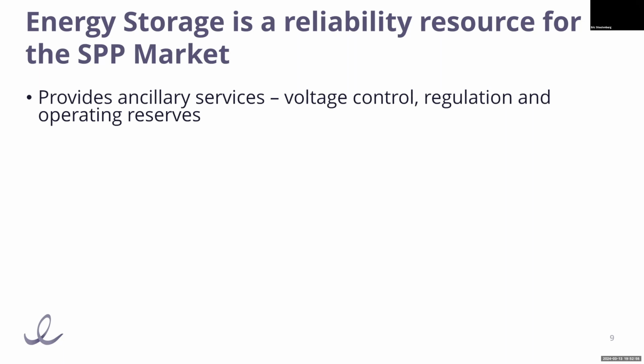Regulation is the second, the second-by-second management of the power system to keep us at 60 hertz. That 60 hertz is a measure that the amount of generation and the amount of load are equal to one another. When those get out of whack, the frequency gets out of whack, and all the battery storage systems respond immediately to frequency deviations without any human intervention.